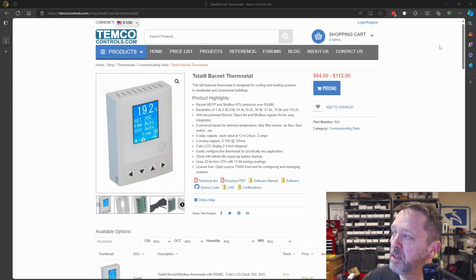Now, if we take a look at this device, this is Modbus RTU, which is a serial that sits on RS-485. What that means functionally is that you can have multiple devices that are hooked onto the same serial bus. So you can have 2 serial lines that run across, say, a building or a plant floor or whatever, and you can have multiple devices on that.